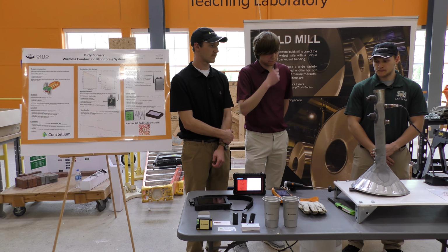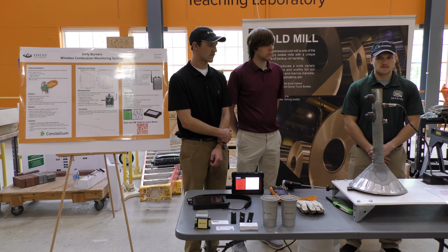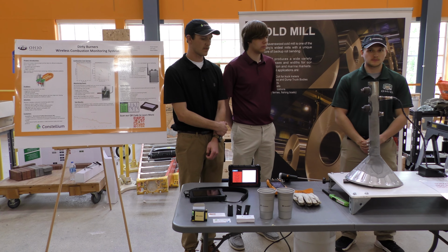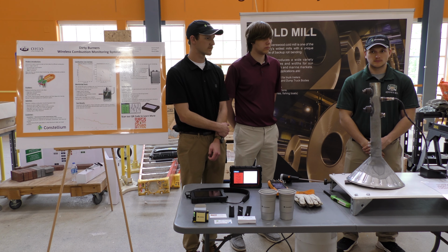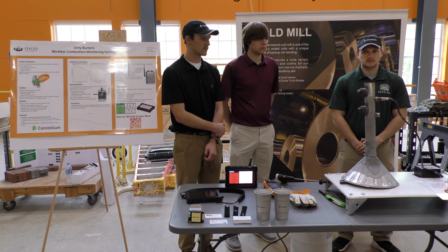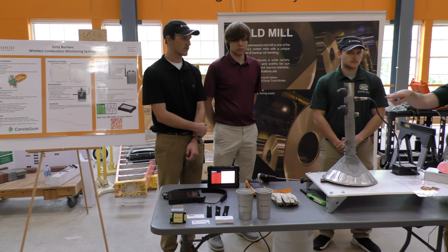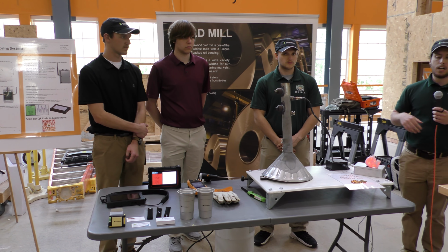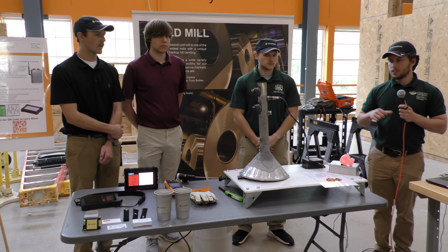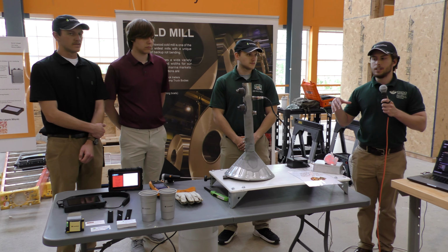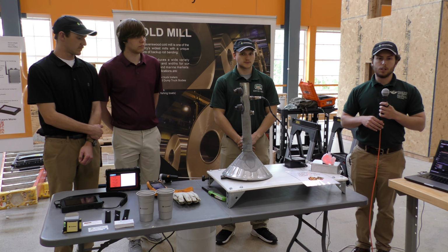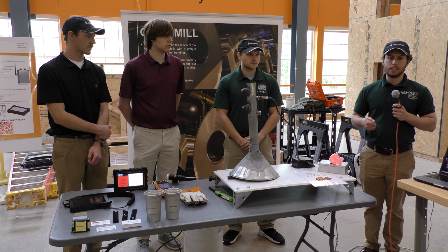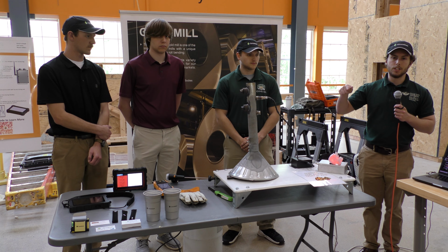The way our system works is there are burners on these furnaces, 16 per furnace. Each one of those burners gets one module that we've made, which you can see right here. Those modules control a sensor that monitors the oxygen levels. This data is collected by us, and we send it over to a plant network so they can have a log of their data, and we also send it to a tuning device so they can tune the air-fuel ratio in real time.